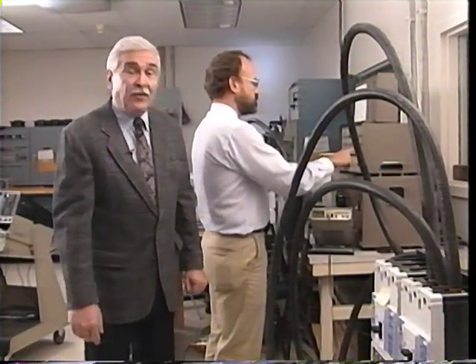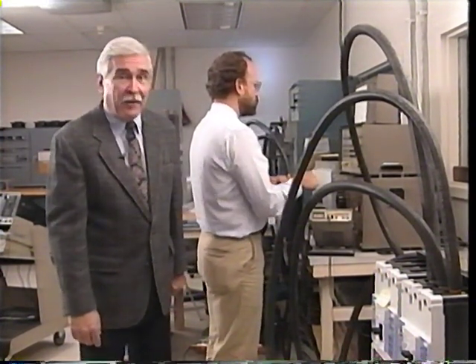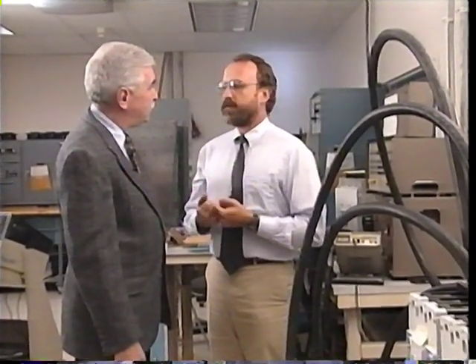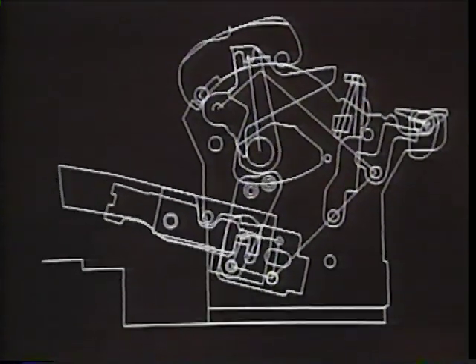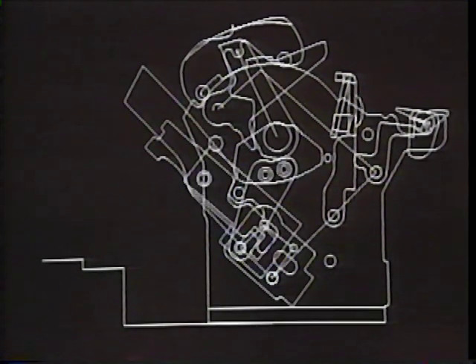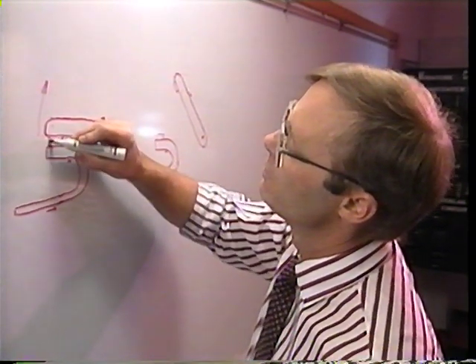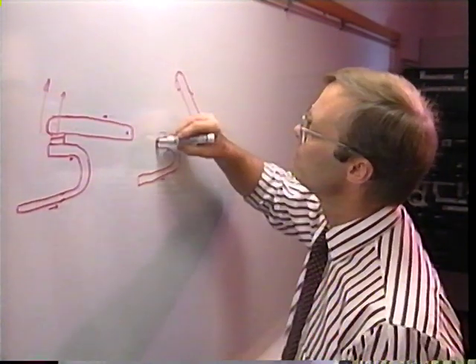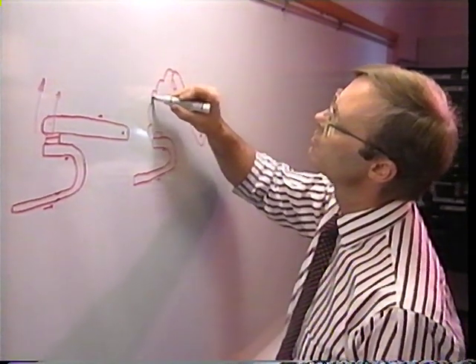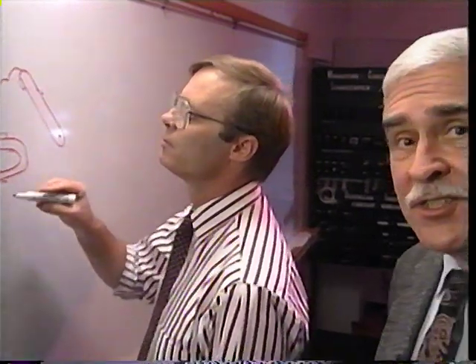And the interaction of technologies doesn't end there. On the other side, those same materials are part of the mechanical device, which has its own demands. The breaker must close the contacts with enough force to reduce the electrical contact resistance, but must also withstand electromagnetic repulsion forces, which can be up to 10 times the rated current of the breaker. Clamp tight when closed, fly apart fast when opened. A tall order. Then consider the contact mechanism itself, where physics and engineering again blend to provide an ingenious method. In the Series C breaker, the speed of the opening motion, with the contacts separating at an acceleration greater than a bullet being fired from a gun, acts with the electromagnetic field to create this long curving arc. The arc limits the fault current and provides the Series C's outstanding current limiting capability. A simple arc, but to make it, you must interweave in an instant the forces of acceleration and electromagnetism.